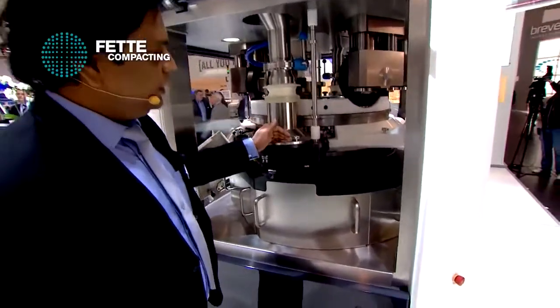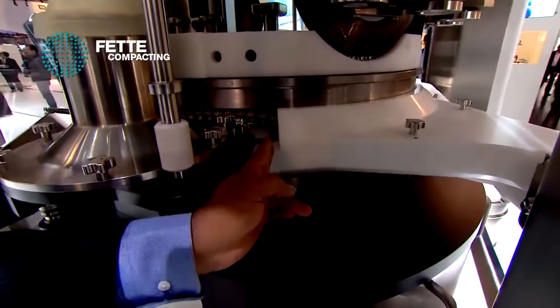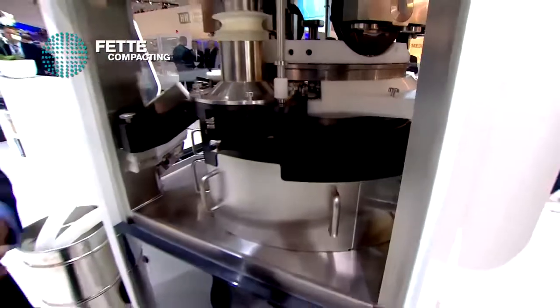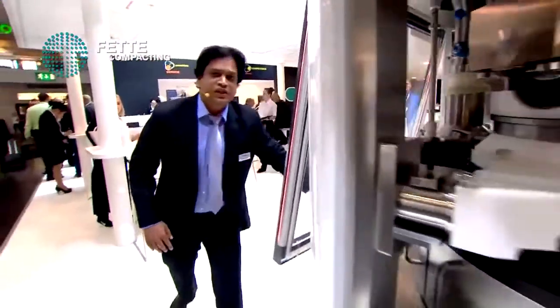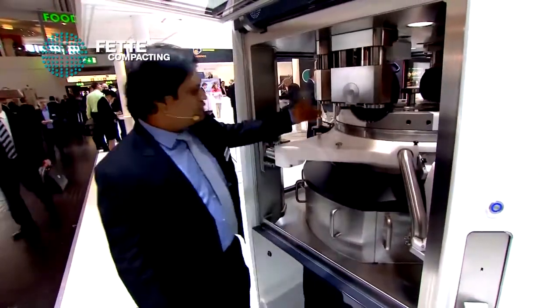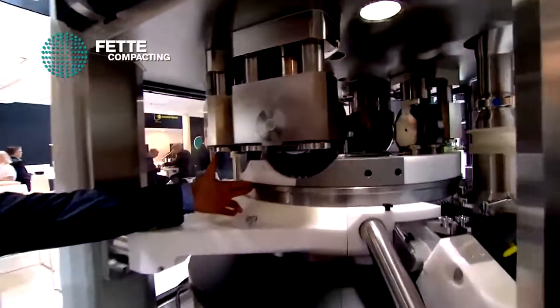When the granules are coming from the feeder to the die-table cavities, we have a pneumatically controlled scraper system that can be actuated from the HMI, which helps you optimize the yield in production. The turret is also an essential part of this machine. With possible use of 115 stations, we can achieve production of 1.6 million tablets per hour.